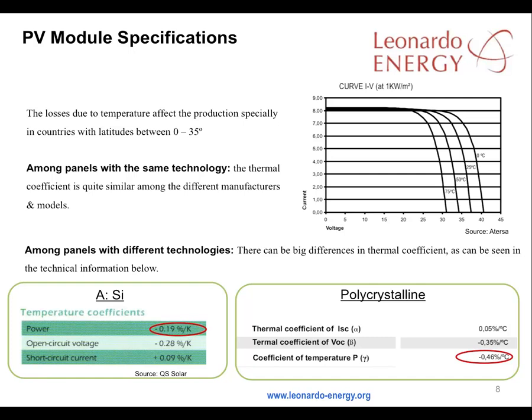Losses due to temperature affect production, particularly in countries near the equator with latitudes between 0 and 35 degrees. Where the panels use a matching technology, the thermal coefficient is quite similar between different manufacturers and models. Where the panels use different technologies, there can be big differences in the thermal coefficient and in performance, as you can see from this slide.